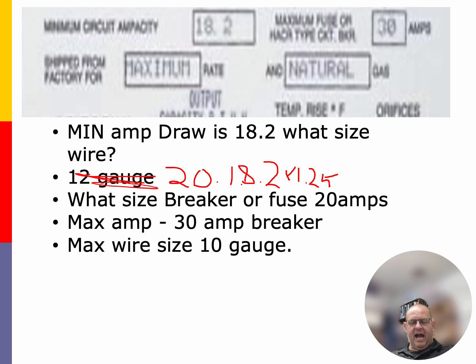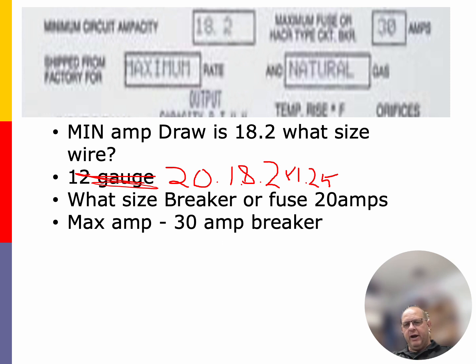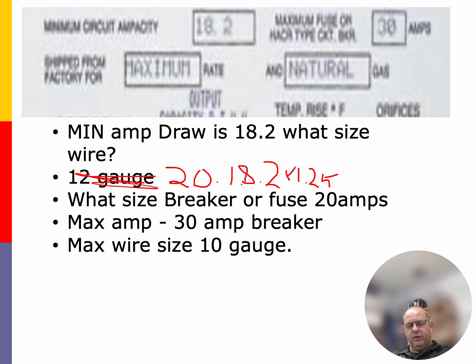And the NEC, the National Electric Code, tells us that we cannot put a breaker in there that's larger than the wire current on there. Plus, we have minimum breaker sizes for the smaller gauge wires that we have, and that runs in a 10 gauge wire. You cannot put it above a 30 amp breaker on a 10 gauge wire.